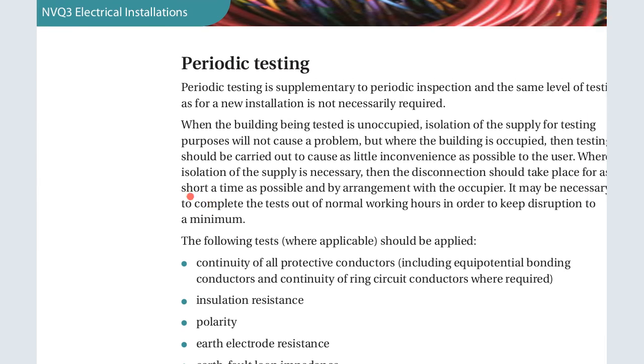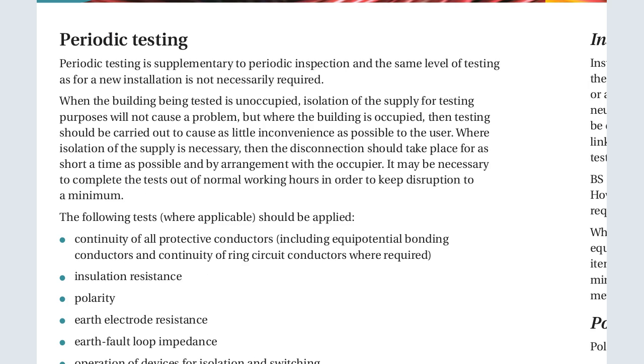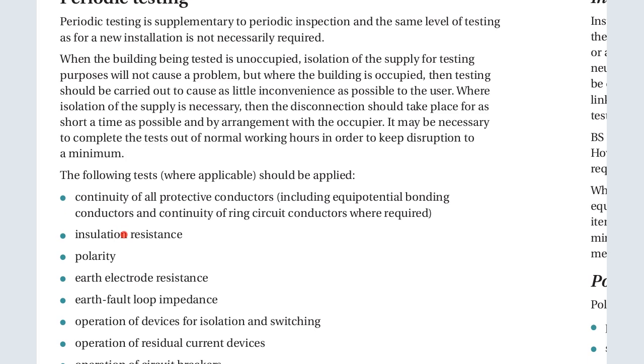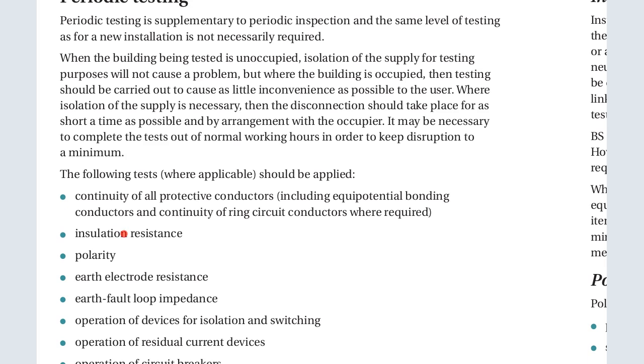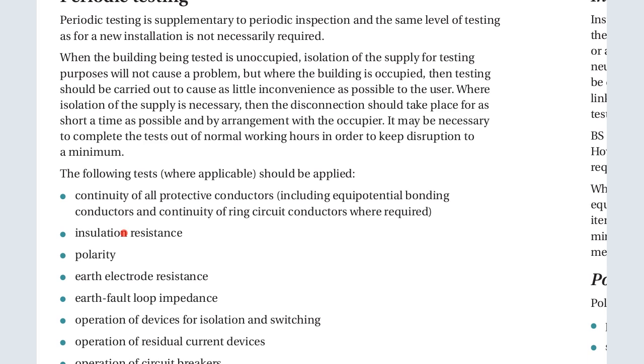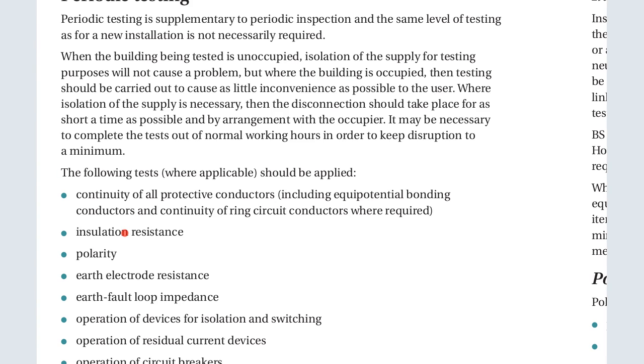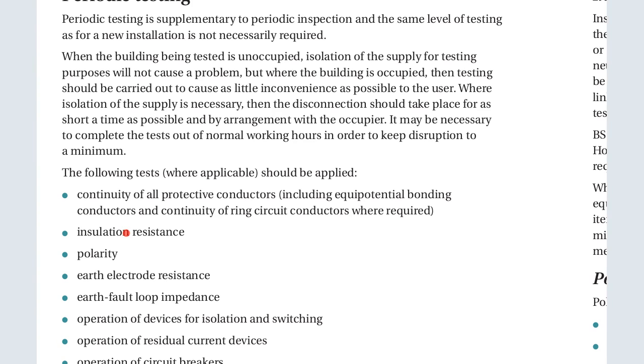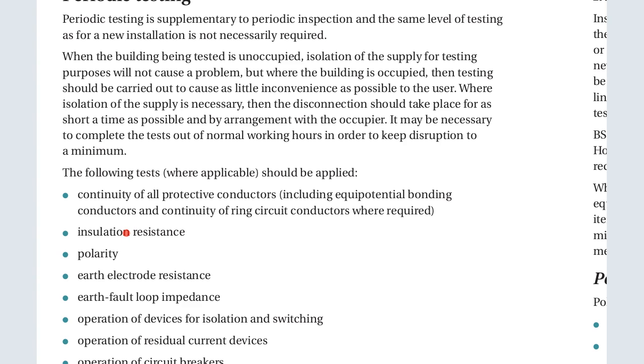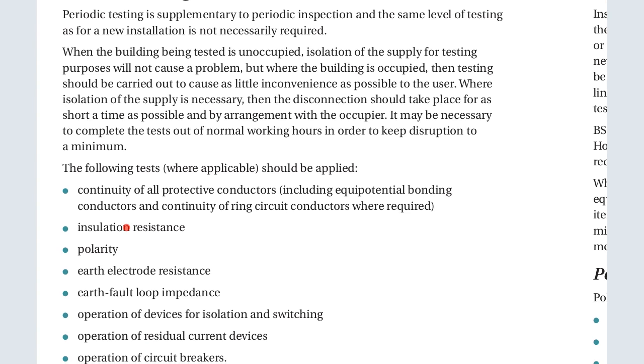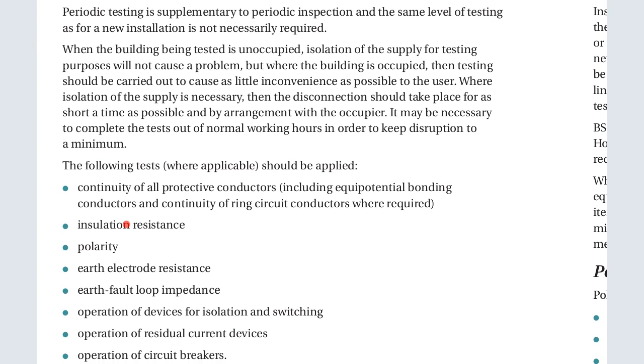Okay. Periodic testing. Now, what do we do in the periodic testing? Periodic testing is a supplementary or periodic inspection. The same level of testing as for a new installation is not necessarily required. When a building being tested is unoccupied, isolation of the supply for testing purposes will not cause a problem. But where the building is occupied, tests should be carried out to cause as little inconvenience as possible to the user. So where isolation of the supply is necessary, the disconnections should last for as short a time as possible. That is the periodic test.